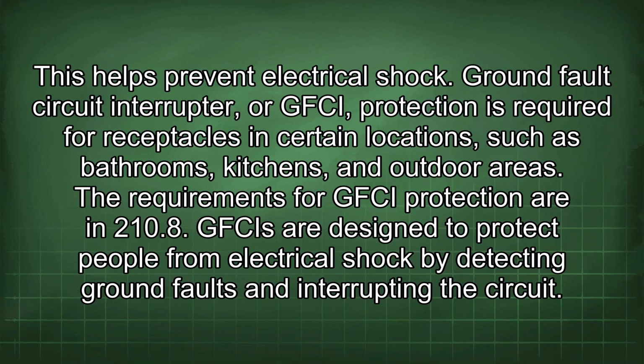Ground fault circuit interrupter, or GFCI, protection is required for receptacles in certain locations such as bathrooms, kitchens, and outdoor areas. The requirements for GFCI protection are in 210.8. GFCIs are designed to protect people from electrical shock by detecting ground faults and interrupting the circuit.